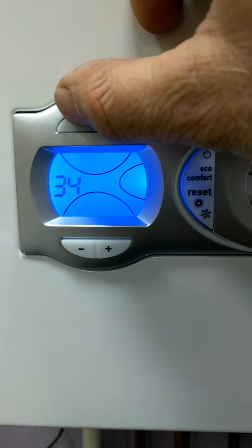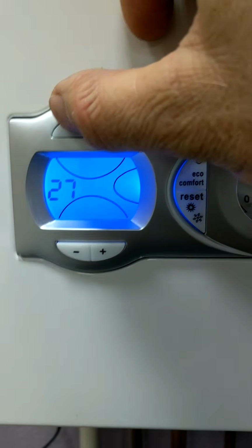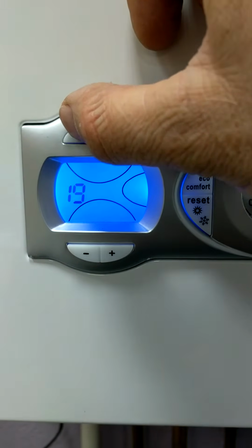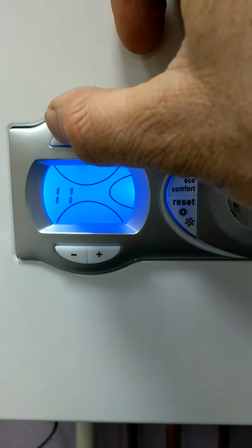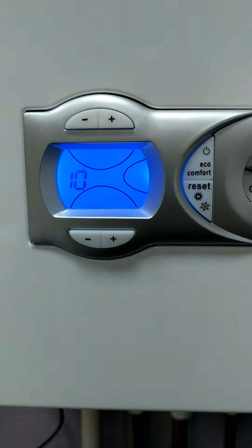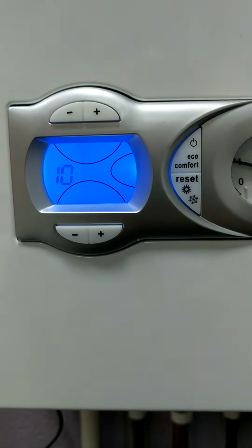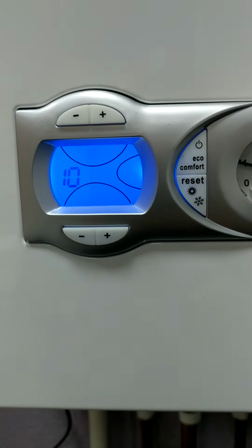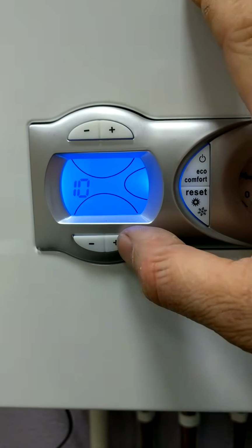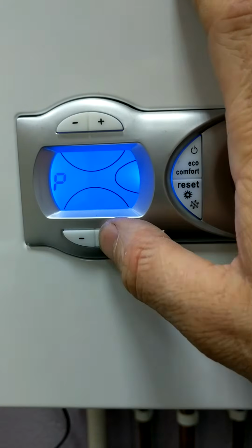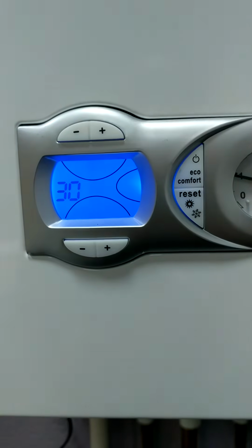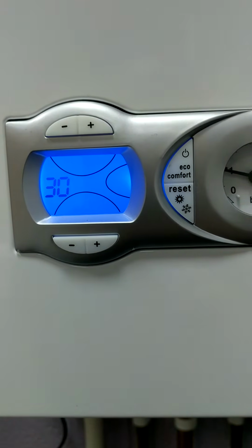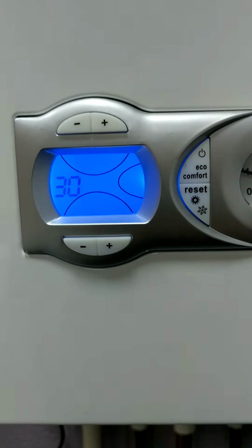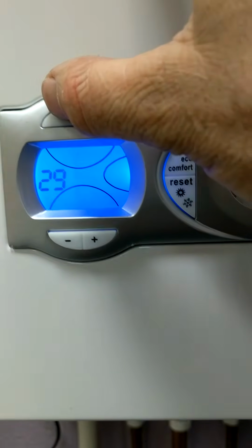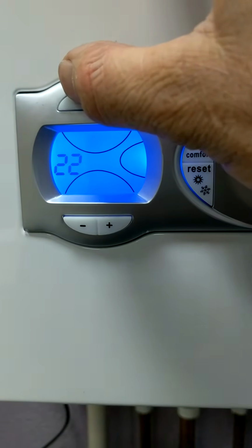So that'll help in the morning when everyone's having a shower, using the hot water. Within 10 seconds, it can get back on and do its job again. So that's the parameter 8 hot water delay. We're going to knock that down to 10 seconds. Then we've got parameter 11, which is the hot water output. The pump overrun. We're going to knock that down to 10 seconds as well.